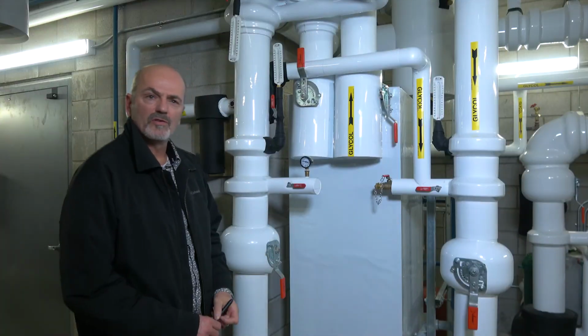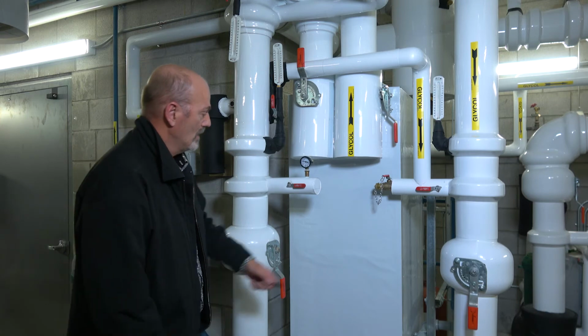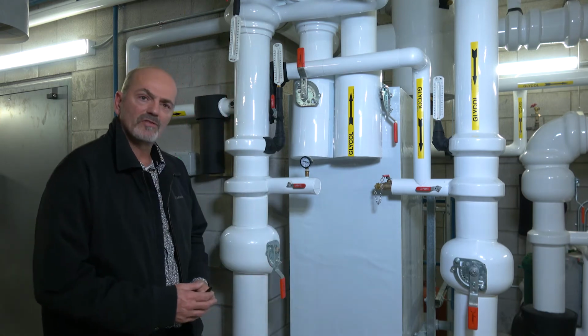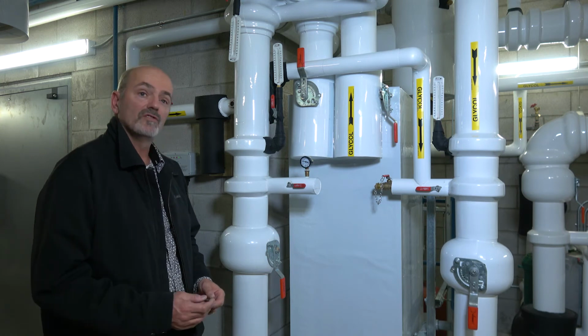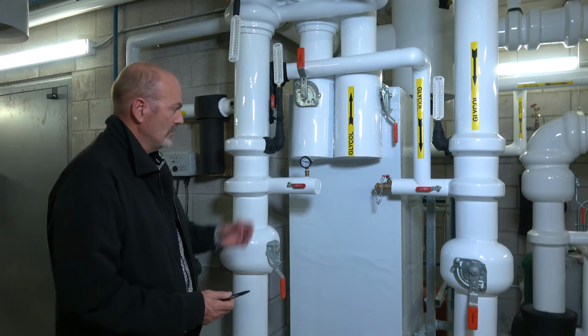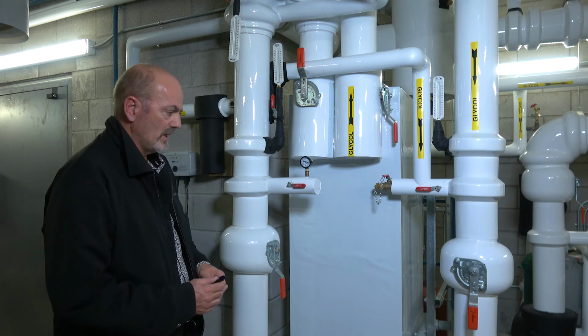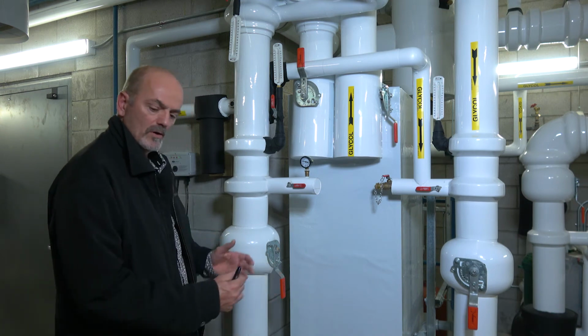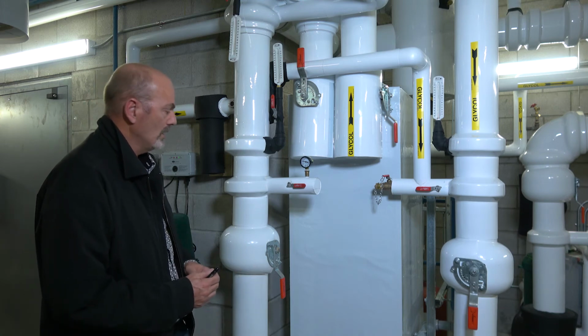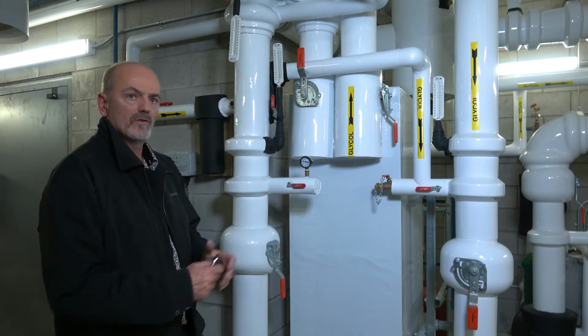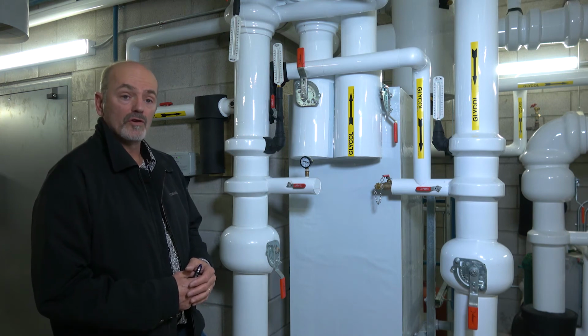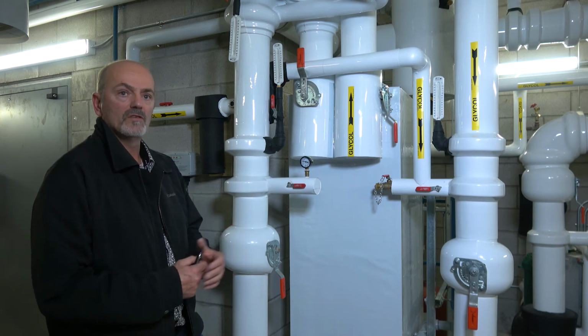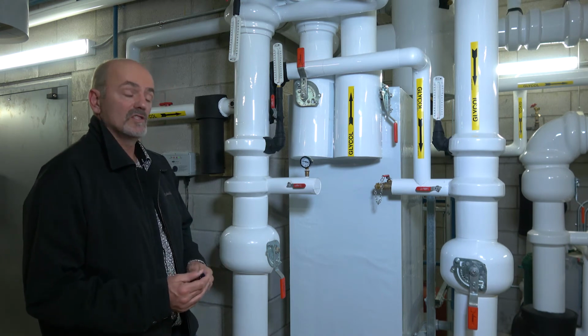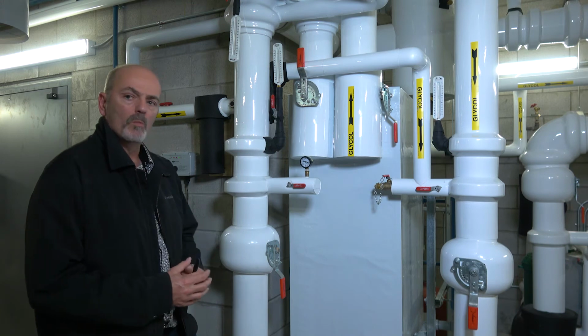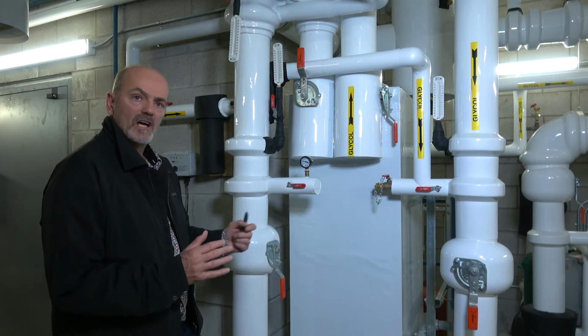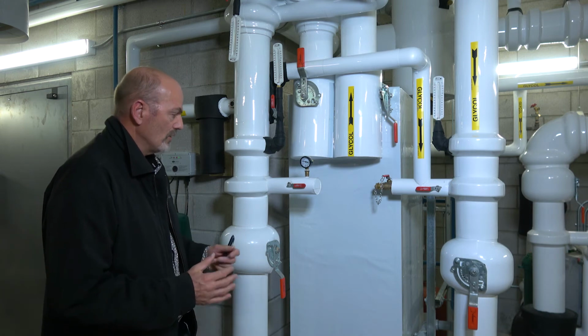This particular piece of equipment is known as a gasketed plate frame heat exchanger. Underneath all this insulation, which is in place to stop it from sweating because it is chilled water for cooling the building, there's a glycol loop to a cooling tower, which has the glycol in it, and then there's the chilled water on the building side, which is just 100% water. It's designed to allow transference of the chilled water, cooler glycol water from the tower into the chilled water. Okay, so it's known as a heat exchanger, and there's really no maintenance to this. It's been factory assembled and pressurized and to tolerances.